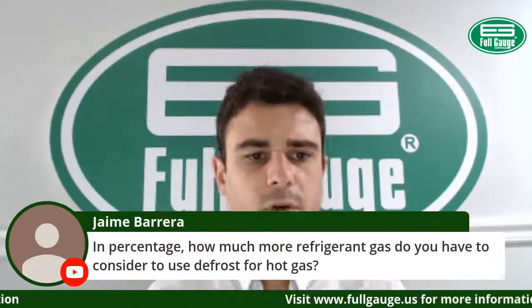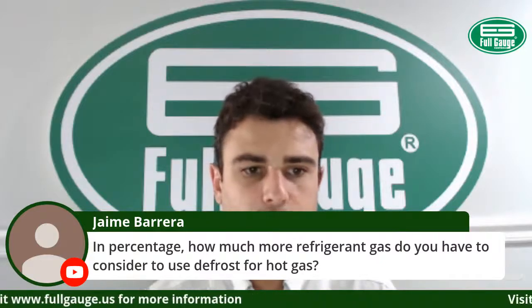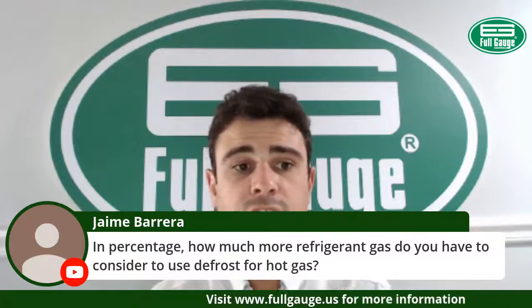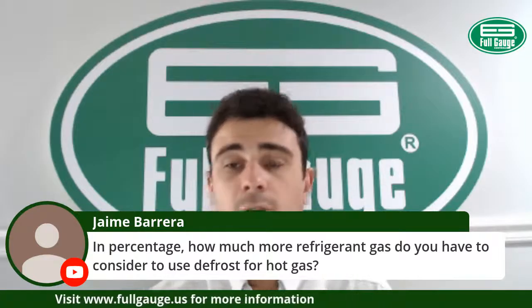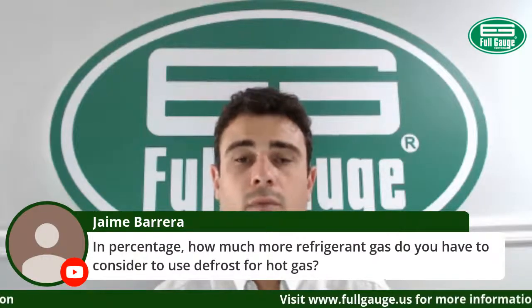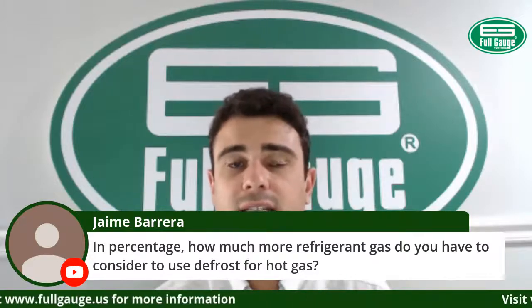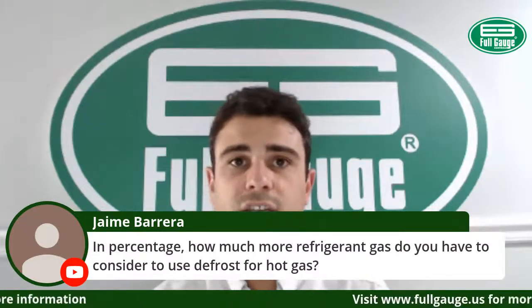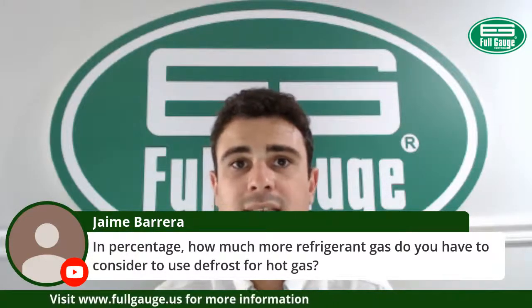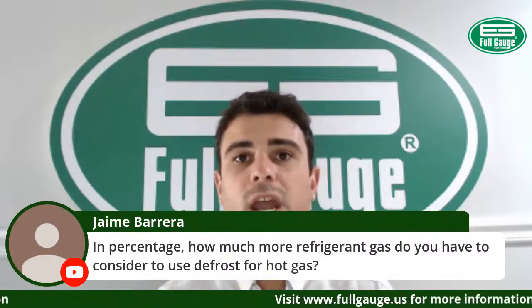Here's a question from Jaime Barrera. In percentage, how much more refrigerant gas do you have to consider to use hot gas defrost? It's a very good question, Jaime. However, this will depend on what design you have used for the hot gas system. Different manufacturers have different designs. During this presentation today, we brought a design that is commonly known as a reversing cycle device, which makes use of a four-way valve.